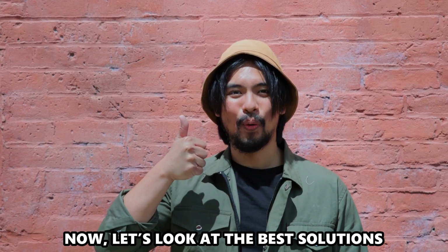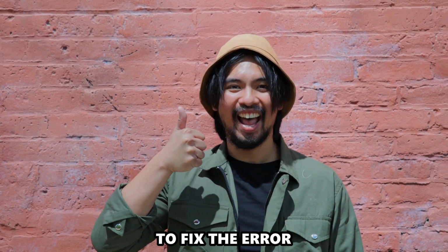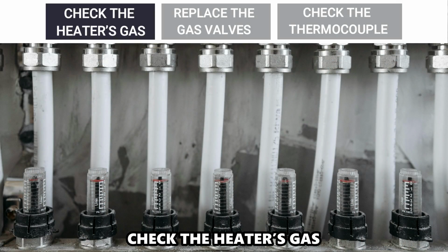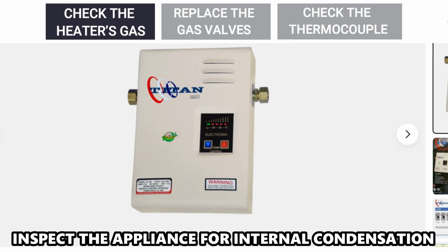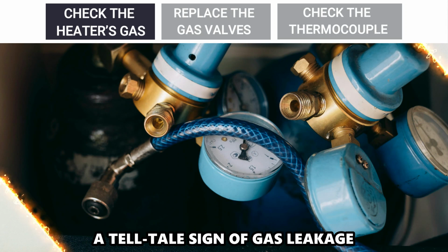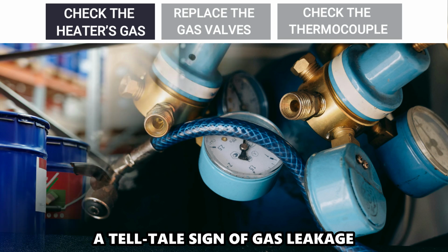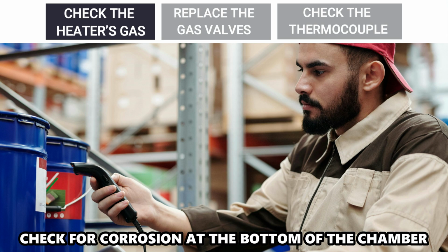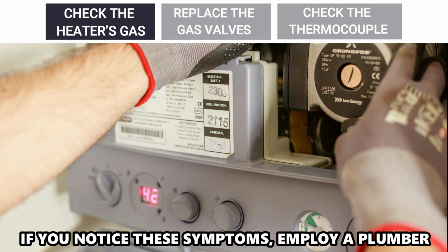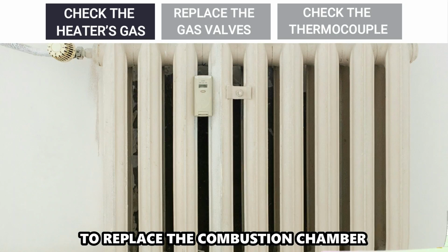Now, let's look at the best solutions to fix the error. Check the heater's gas. Inspect the appliance for internal condensation in the combustion chamber, a telltale sign of gas leakage. Check for corrosion at the bottom of the chamber. If you notice these symptoms, employ a plumber to replace the combustion chamber.